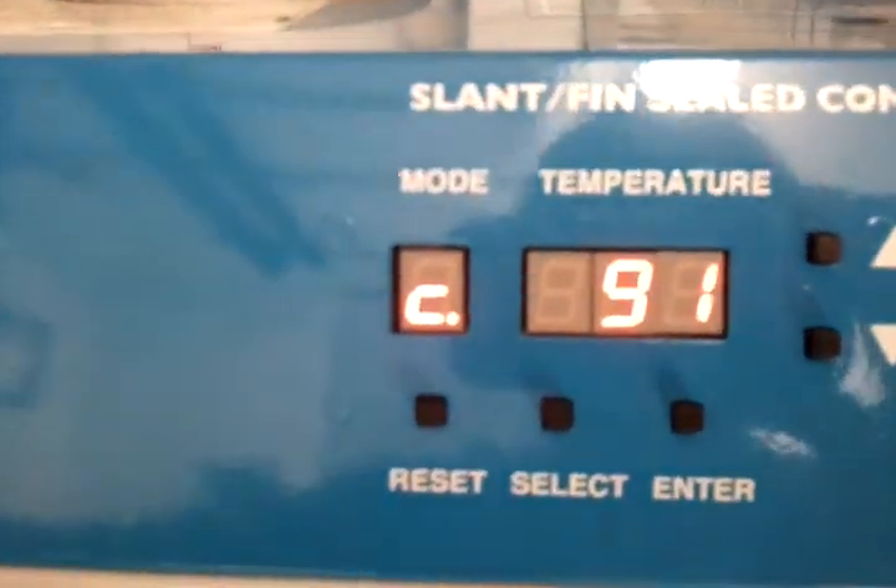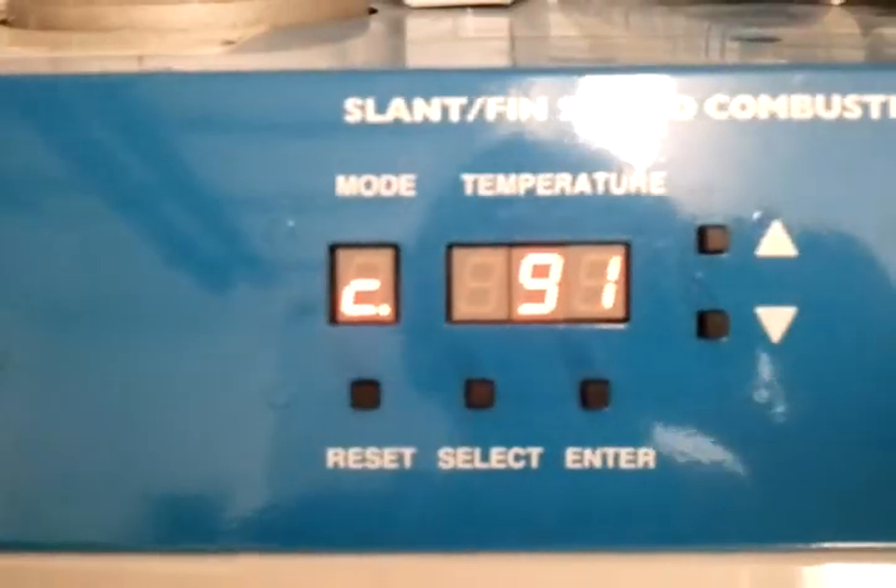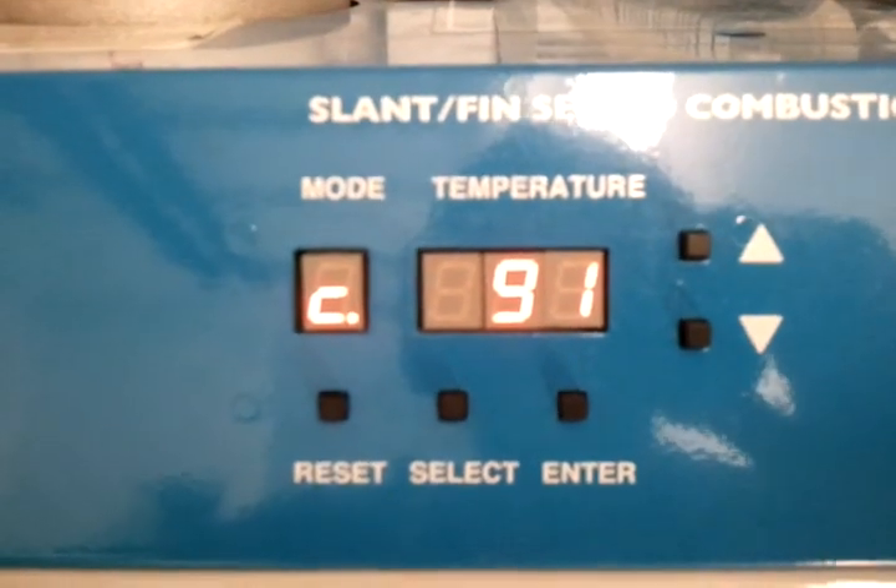There are two copper coil heat exchangers in there. That loop of pipe is the same water that's also going through our radiant floors. If you look at the boiler, you can see there's 91-degree water flowing through there, but that blinking dot means we're not using any gas.